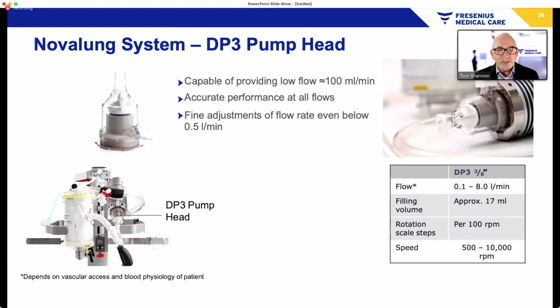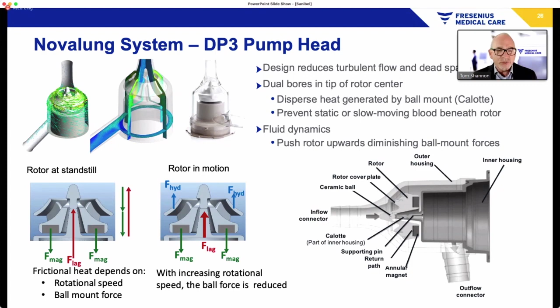We call it a diagonal pump, mostly because of the elliptical pathway as the blood passes through the impeller. If you notice, the impeller sits on top of a housing within the centrifugal head. So the blood has to pass the impeller. It doesn't spend a lot of time within the impeller itself. The transit time is pretty quick, but because the pump head is so small, the RPMs will be a little bit higher than you're used to seeing with other centrifugal pumps, but that's its normal pattern.